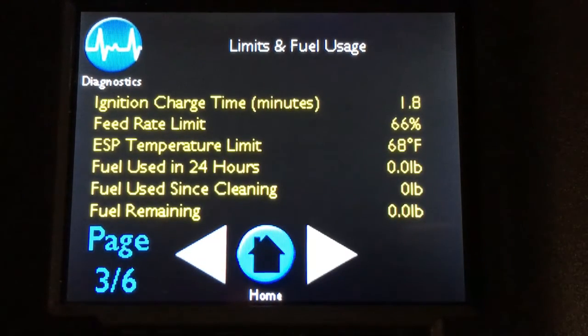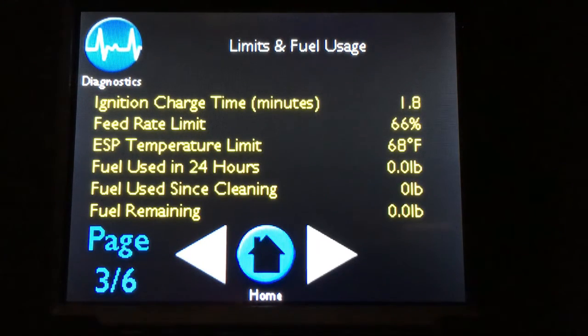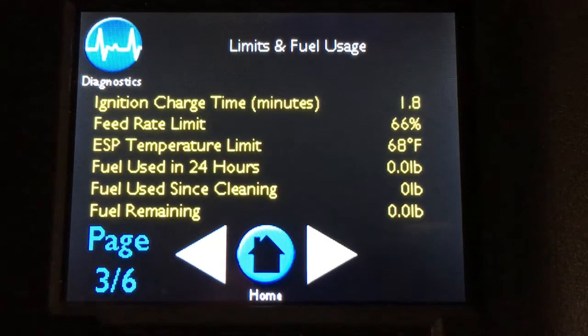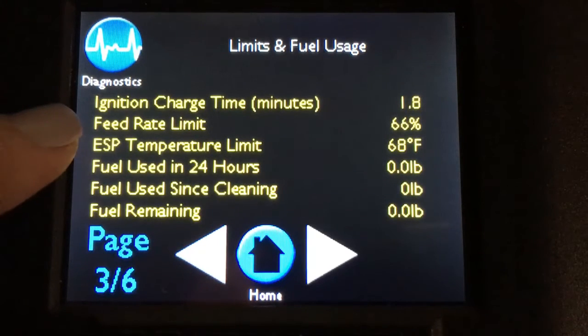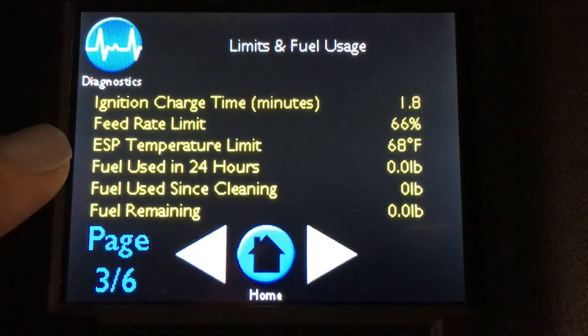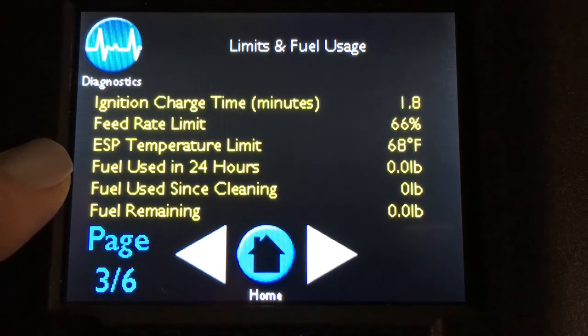The third page displays limits and fuel usage. The ignition charge time displays the amount of time the auger feeds fuel during the ignition cycle. This is only altered in the dealer area. The feed rate limit displays the maximum allowed percentage as set in the feed limit screen. Then we have the ESP temperature limit, which displays the maximum temperature of the exhaust sensing probe allowed by the control. This is based on the current setting.